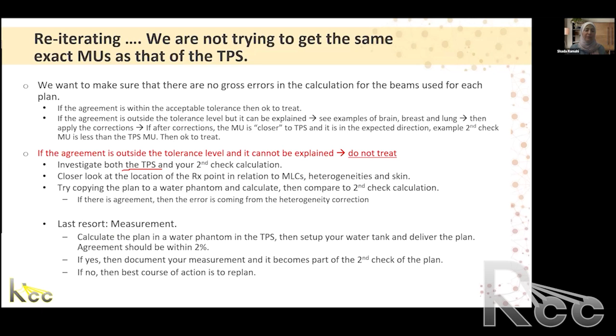And if that is within the 2 to 3%, you can still go ahead. It just means that the actual plan was too complex for your simple monitor unit verification, that no matter how many times you try to assume, presume, work with all these assumptions, it is too complex for the MU check to come up within the 5, 6, 7% that you want. If you calculate in water and you are within 2%, that's good, go ahead and treat. If even within the water geometry, taking the plan, putting it in a water phantom, calculating and then measuring, I don't get 2%, then do not use that plan.